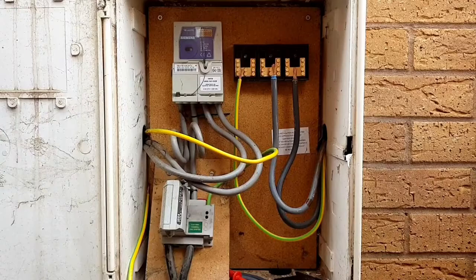Now we've chosen to split the tails for this installation for a number of reasons, which include that it's quite tricky for us to source the correct MCB to go into the spare way of our consumer unit. It gives us an opportunity to add some surge protection into the installation, and also it's important that we demonstrate how this is done so that we can show how to get the current transformer into the correct position on the incoming meter tails. Before we do that, we're going to have to safely isolate the supply.